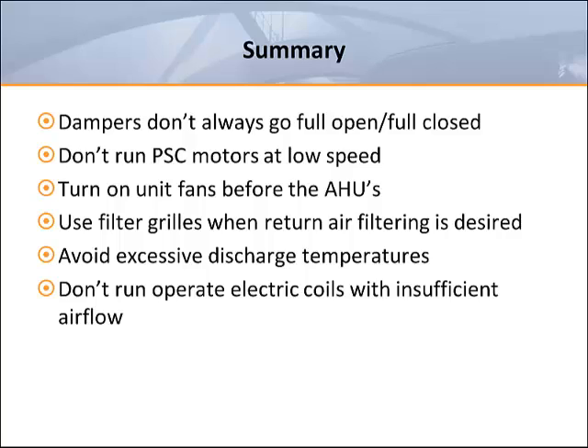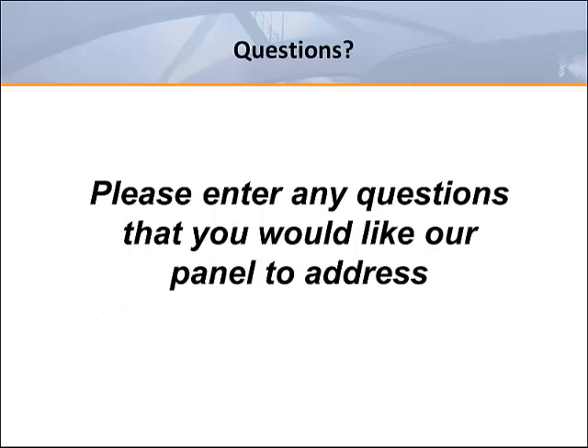Hopefully we've covered all that we meant to cover. Just remember that terminal unit dampers don't always go full travel, and don't select PSC motors to run at low speed. Always turn on your series fan boxes before you turn on your air handlers. If return air filtering is deemed necessary, use filter grills for easy access. Also avoid high discharge temperatures on electric coils and never operate them until the system has been balanced to ensure proper air flow. That concludes our program today. We thank you for spending this time with us and hope that this material will benefit you in your professional endeavors. Our panel will now begin answering questions. If you have any questions, please enter them in the box on the right side of your screen. Thank you and have a great day.